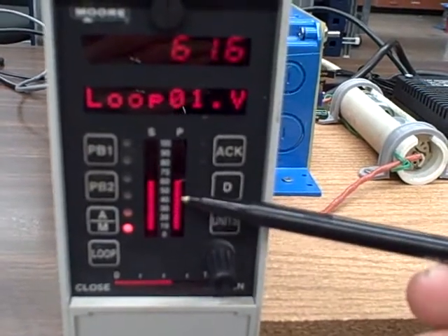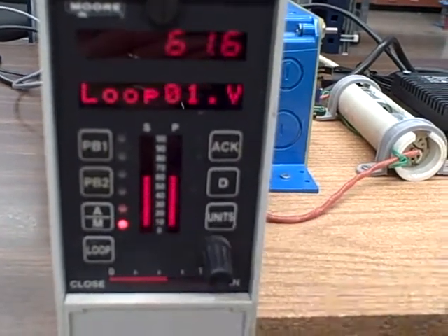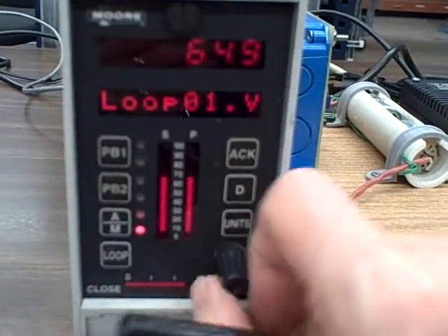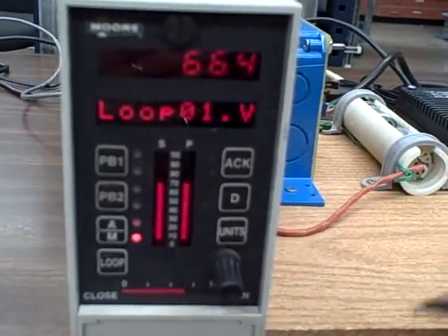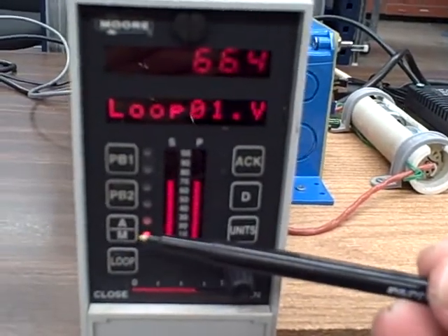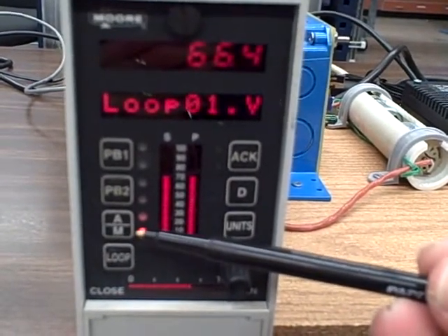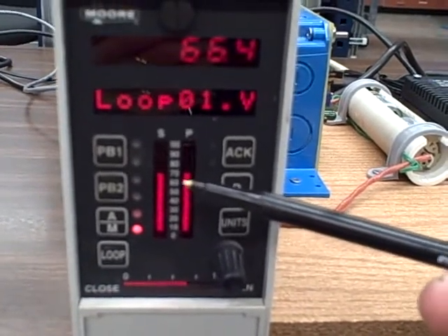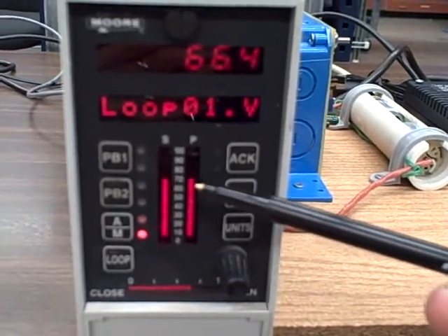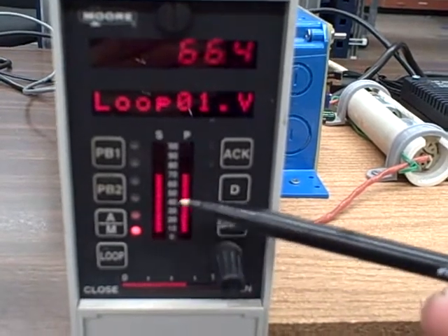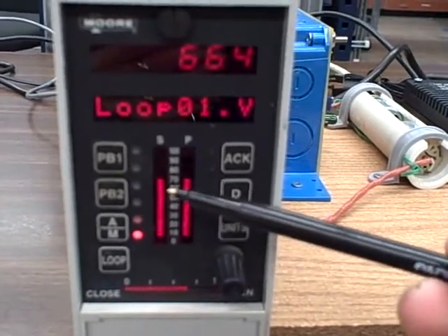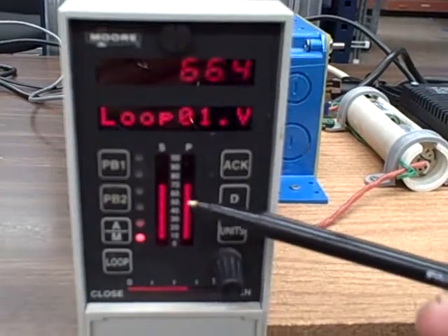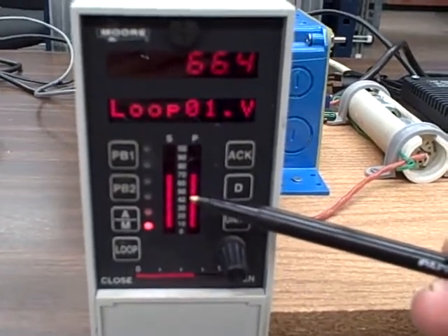The idea of this concept is that when you're in manual mode, you're adjusting the output until you get the process variable where you want it to be, and then when you're done doing that, you're probably going to switch to the automatic mode. And at that point, it is assumed that the process variable is already where you want it to be. So why not just make the set point equal the process variable at all times in manual mode, so that when you switch to auto mode, the set point's going to be right there where you left the process variable. That's the notion, that's the logic behind set point tracking.